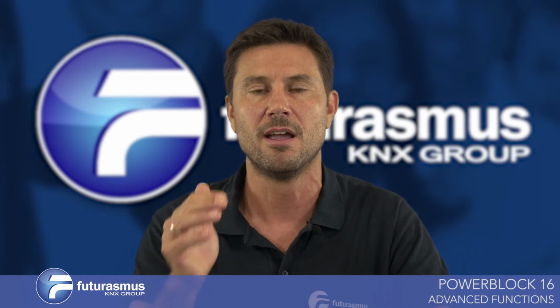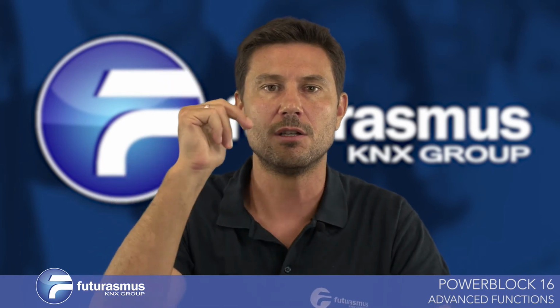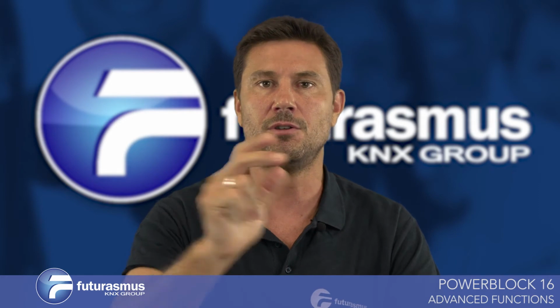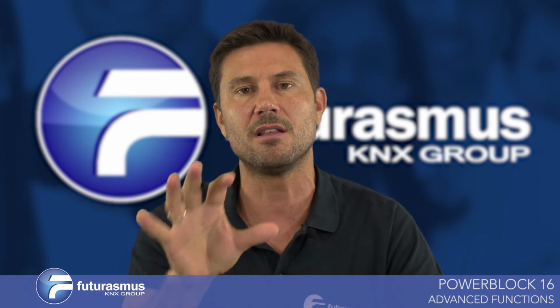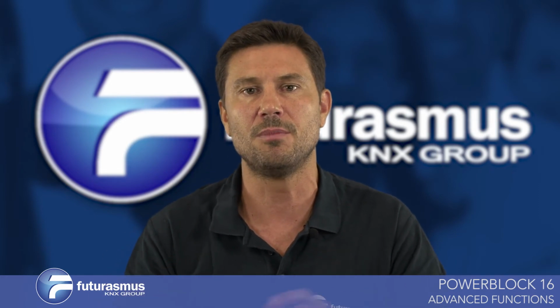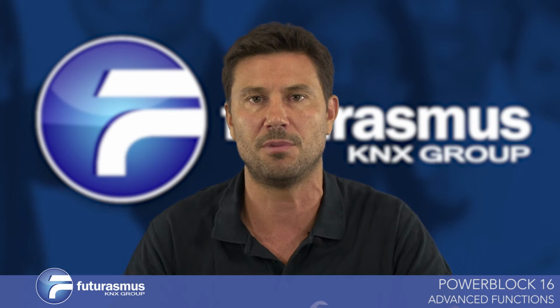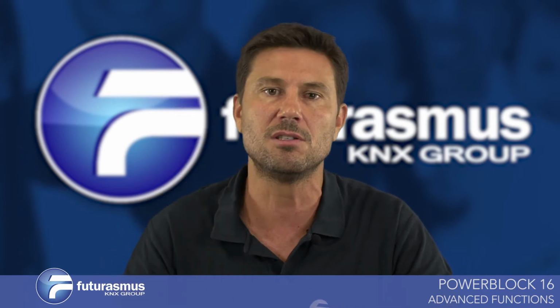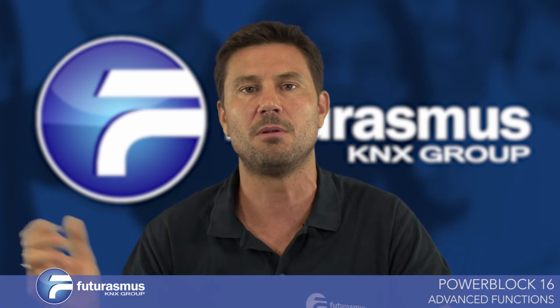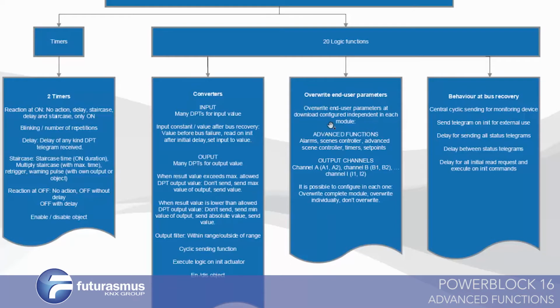For instance, you can say I want scenes number 1, 2, 5 not to be overwritten, because those are the scenes the customer told me he has changed. All the others should be reset to the default values which were set in the application program. So you can go into those functions, set those scenes not to be overwritten, and the rest will be overwritten. This is very important, that your device has this possibility.